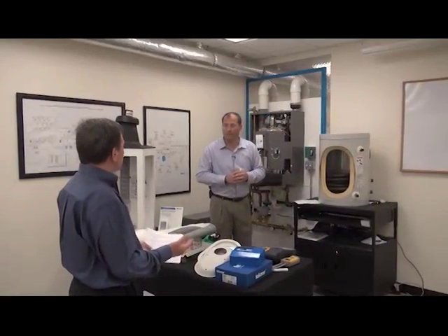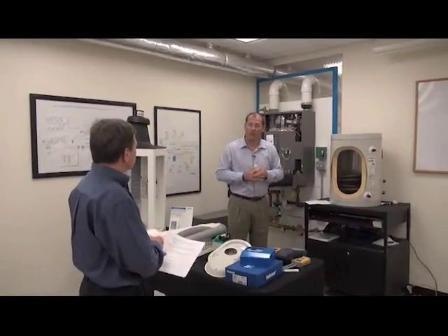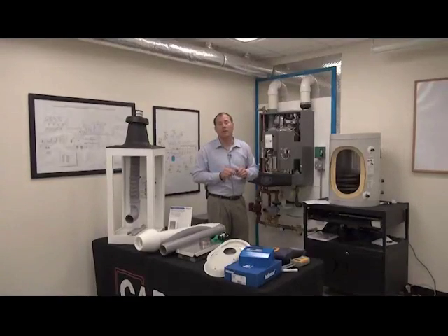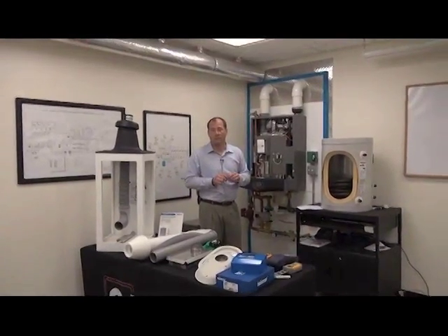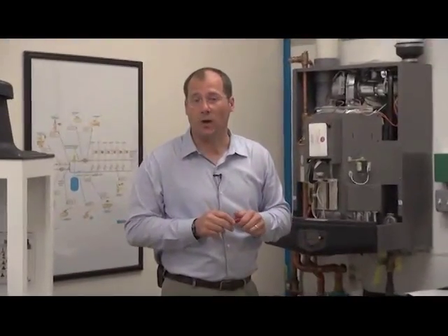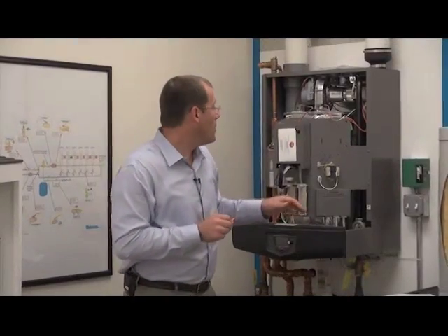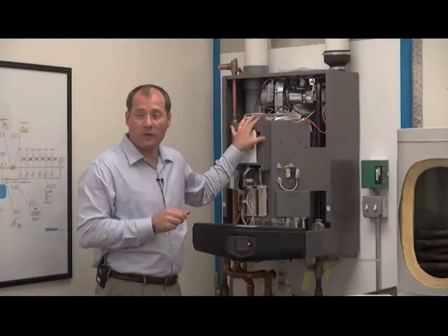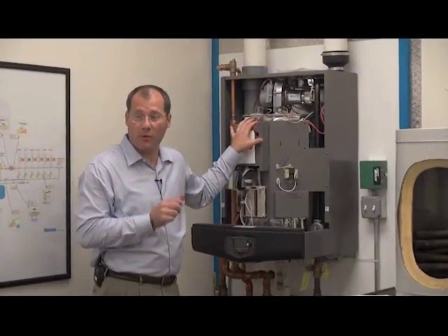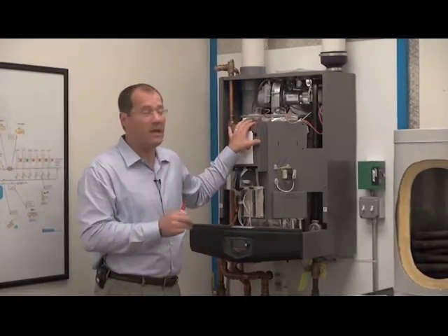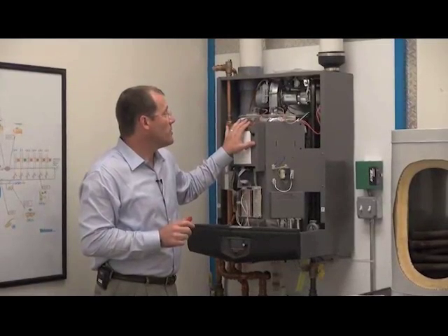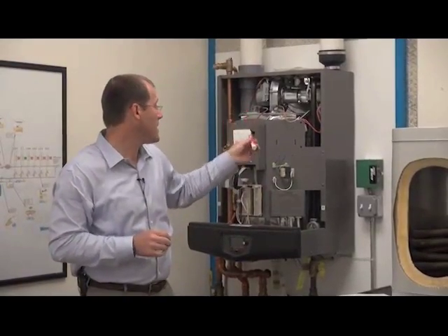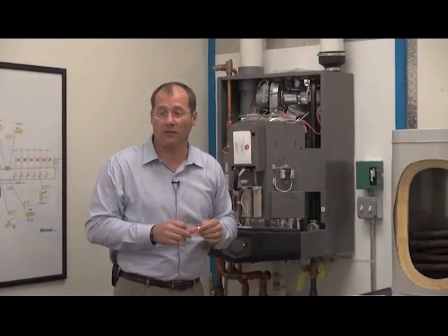And so why should I be concerned about short cycling? When we talked about the older boilers having very few moving parts, newer boilers have many moving parts. And cycling is what reduces their life. So just this technology is reducing the useful life expectancy of newer equipment to about 15 years, properly maintained, properly sized. And if we start to put thousands and tens of thousands of cycles on the fan, on the igniter, it wears them down and you'll have higher service costs.